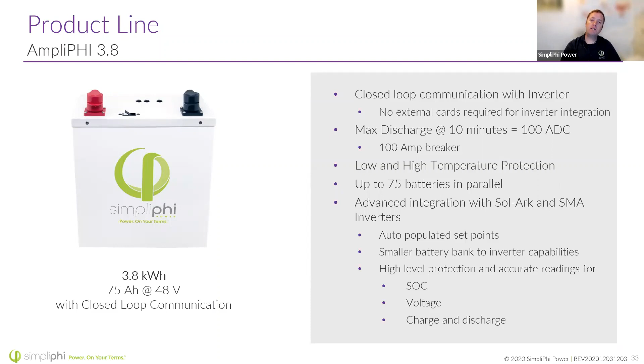So back to some of these extreme temperature environments - if you know you're going to be in some of these cold environments, think about the SimpliPhi, because it's going to tell the equipment, hey, it's starting to get cold, let's ramp down some of this charge rate, or hey, it's too cold, stop charging me. This has built-in thermistors inside the battery so that it knows its internal temperature and can offer that higher level of protection. We're limited to 75 batteries on the SimpliPhi, which is still a huge system, just because of the limitations on the communication runs. And those communications allow a much higher level of protection, like I mentioned, but also much higher accuracy readings of its state of charge, voltage, and charge and discharge, because the battery internally is telling the equipment that, not the equipment trying to figure out what the battery is doing.